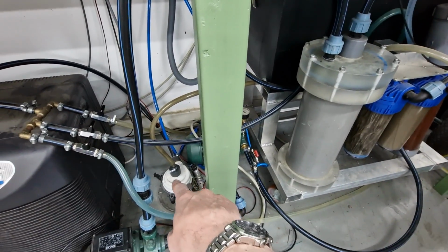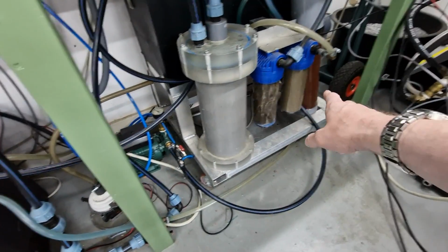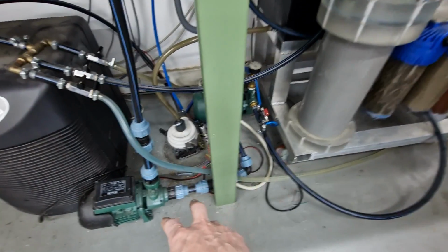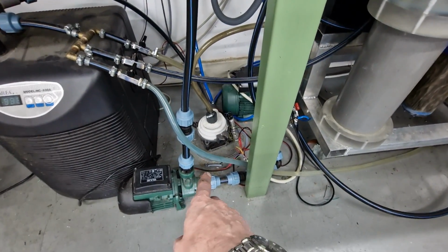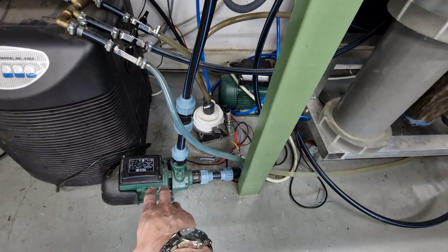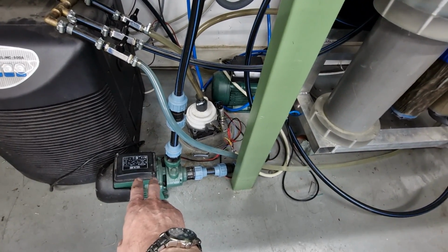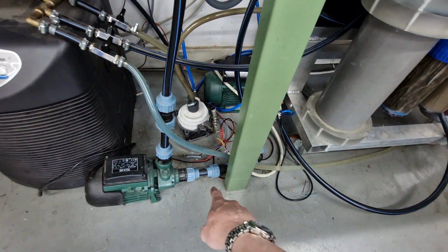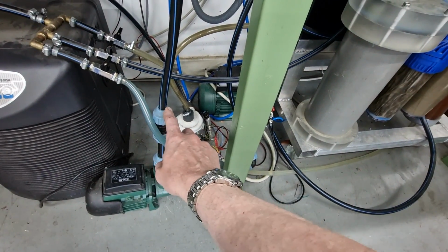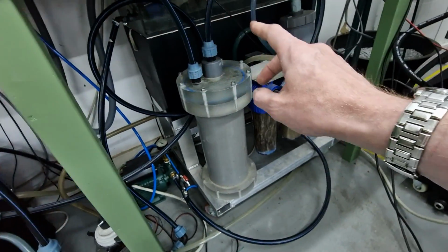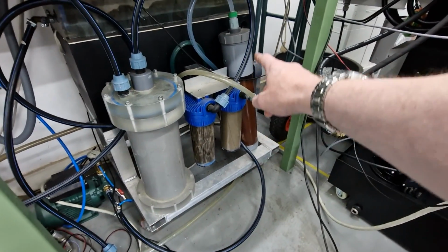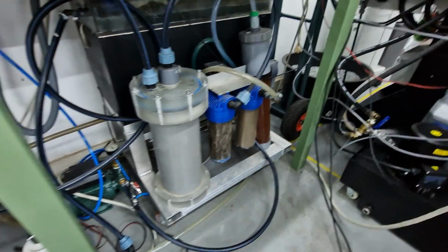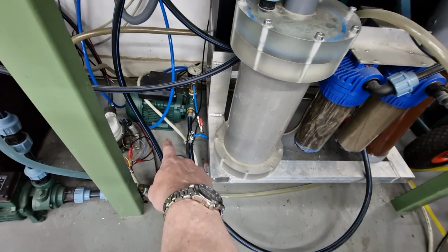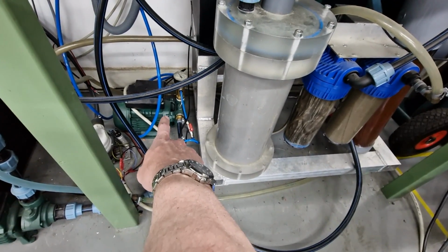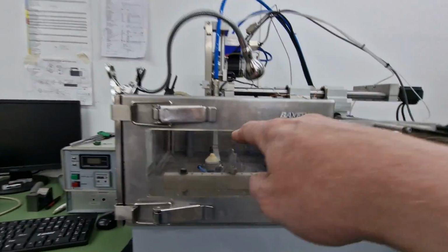That's the one which I use to fill the tank and to perform the deionization. And here are the 2 other pumps that I use to replace the dishwashing pumps. Here's a big centrifugal pump that I use for water cleaning. It sucks in dirty water and spits it out at pressure, forces it through these filters, turns it into clean water, and then it goes into the clean water tank. Then there's the pump in the back, here. It sucks in clean water and forces it at high pressure, 10 bar, to the flushing nozzles in the machine.